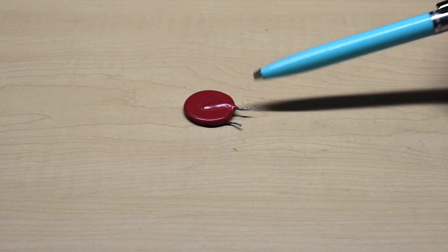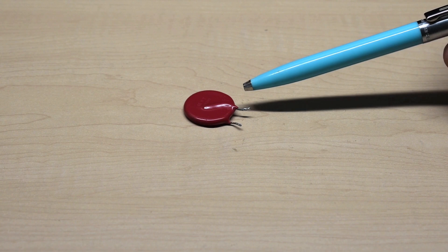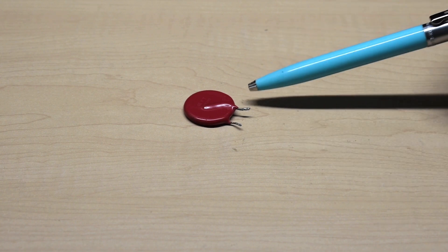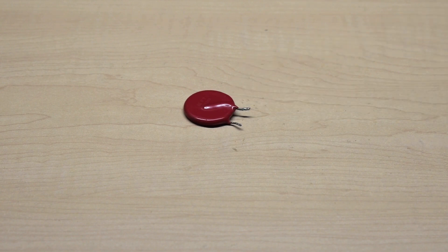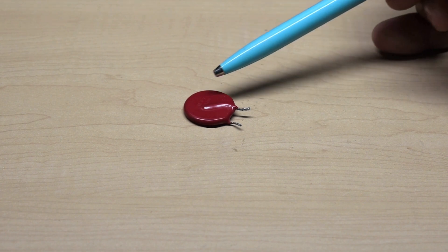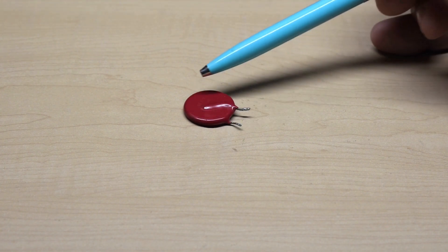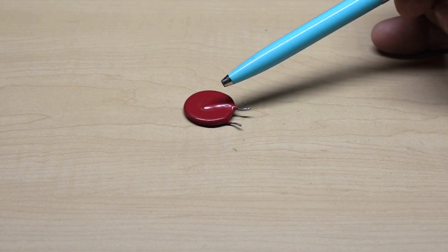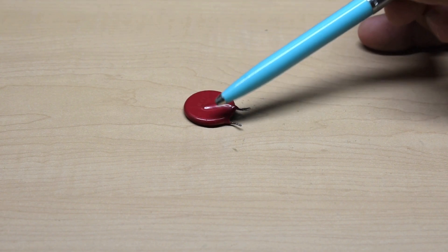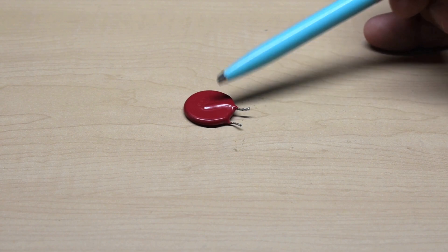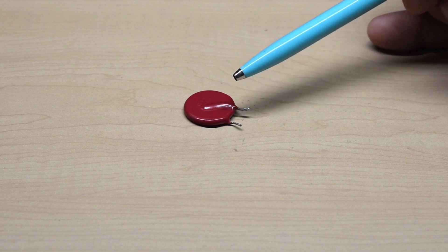The 150 refers to 150 volts AC continuous voltage. If you're going to be using this with DC, it's rated 200. How much energy or joules the device can handle is directly related to the size. So this one here you can see is about 20 millimeters in diameter. That's what the 20B means. If you have the same thing and it's thicker, so the same 20 millimeters and thicker, it's going to be able to handle more energy in the event of a lightning strike.